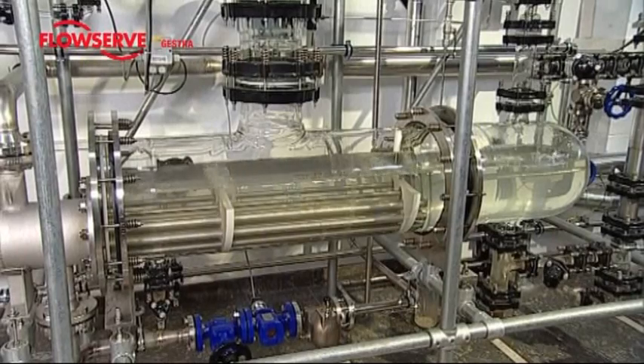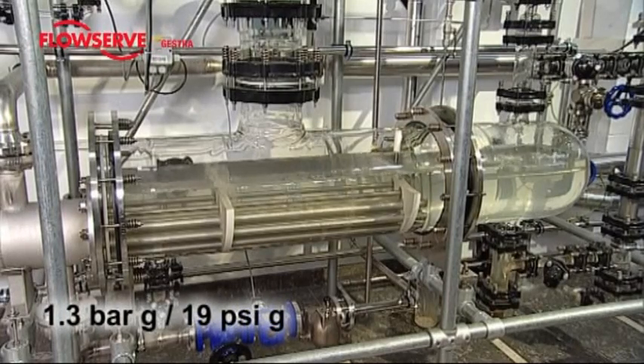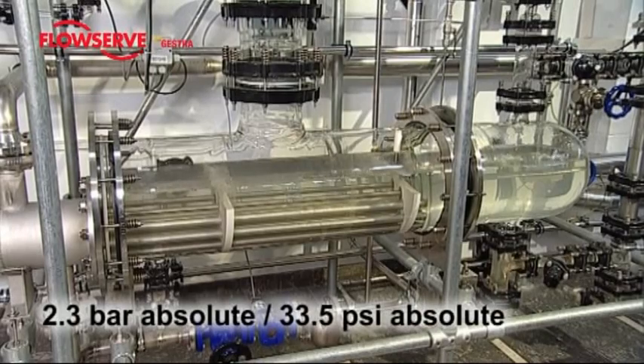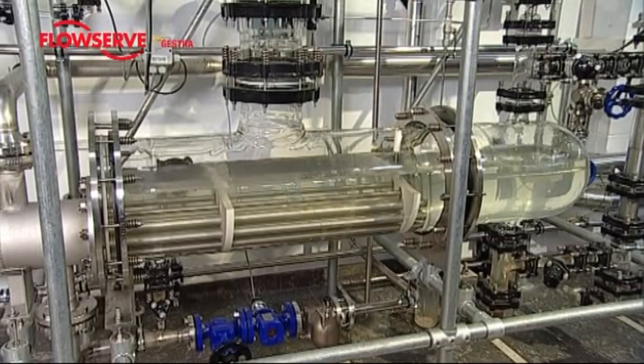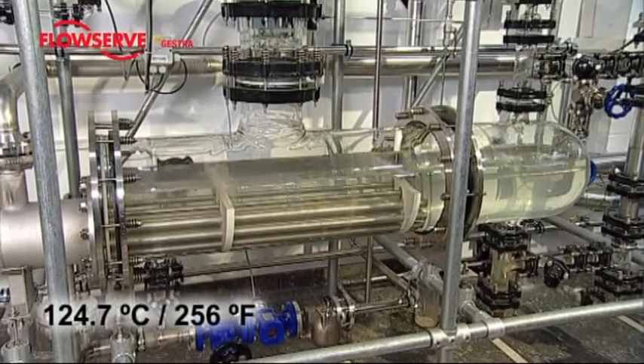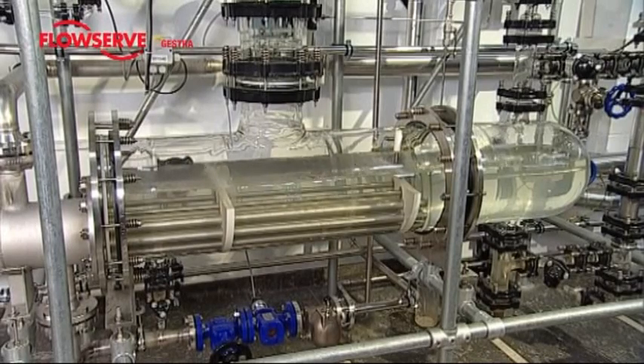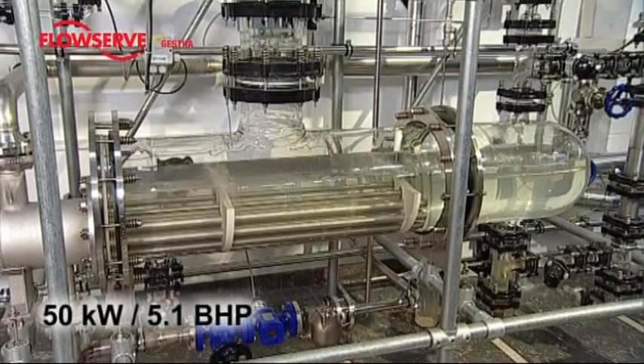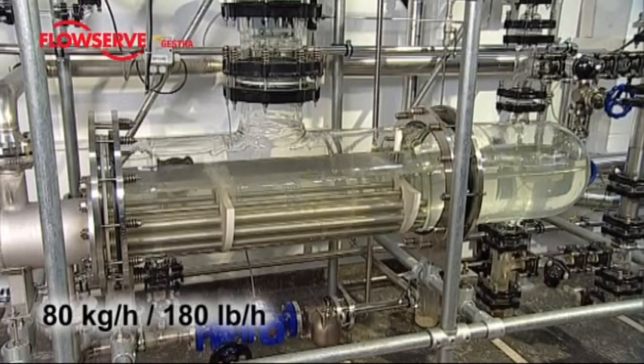This video shows the thermal processes taking place during the generation of saturated steam in a glass steam boiler. This is demonstrated with the aid of the glass evaporator built by GESTRA AG, Bremen. The evaporation process occurs at an operating pressure of 1.3 bar gauge, which corresponds to 2.3 bar absolute. At this pressure, the boiling point as well as the saturation temperature are 124.7 degrees centigrade. The capacity of the steam boiler is 50 kilowatts, which yields a steam flow rate of 80 kilograms per hour.